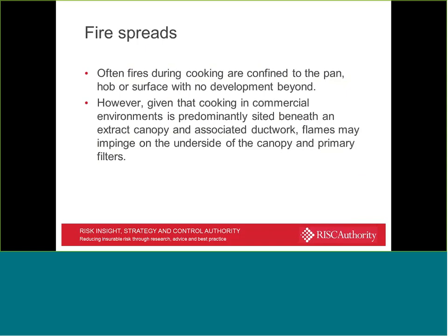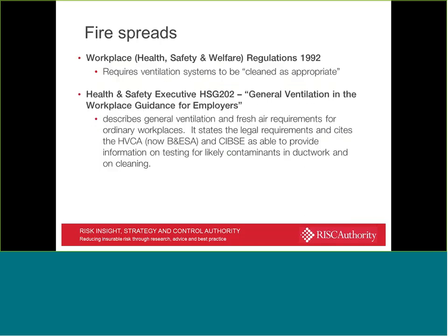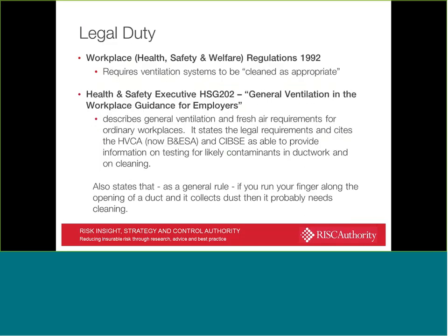The filters are an issue from square one and something we're going to touch on in a few moments. But as I've just described, often the fires aren't confined to the pan, hob or the surface with no development beyond. They do spread, and in commercial environments, whether you've got an extract canopy and ductwork, it's not uncommon for the flames to impinge on the underside of the ductwork, the canopy hood, and the filters themselves.